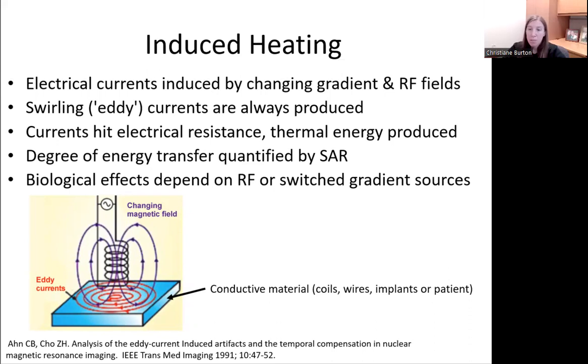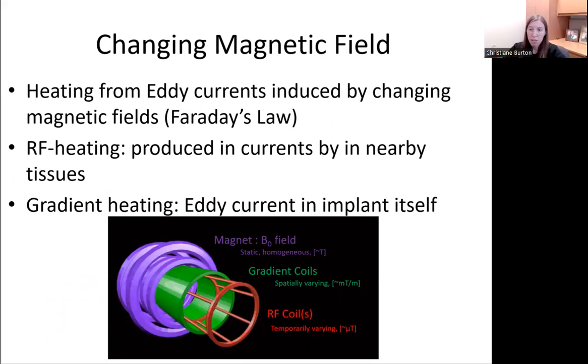The degree of energy transfer is quantified by SAR. So, for example, when a metallic implant is present, energy may be deposited both within the implant itself as well as in the immediate adjacent tissues. What happens precisely depends on the shape and composition of the material and whether we are dealing with RF or switched gradient sources. So there are two ways to change the magnetic field. The first is RF heating produced by currents in nearby tissues caused by implant-related intensification of electric fields. Then there is gradient heating, which is due to eddy currents within the implant itself, with secondary heating of soft tissues. It can be intensified by scattered radiation on the surface of the implant. Just a reminder that the gradient field gives us the spatial localization of signal in MR imaging, and the RF field gives us the grayscale voxel values.